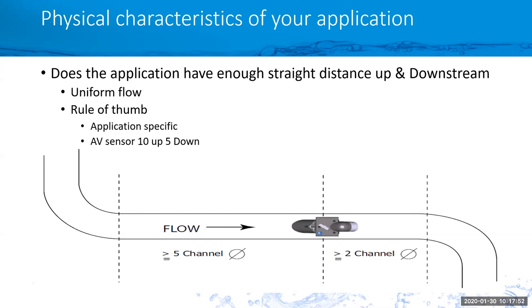Really, it's specific to the application. You have to look at the application and determine what is upstream. Do we have pumps or bends? How fast is the velocity? Because with the faster velocity, we need more straight run. If we have something like a bend or a pump upstream, it's going to create more turbulence. And the idea is we want to make sure we have uniform flow before it goes across or underneath your area velocity sensor.